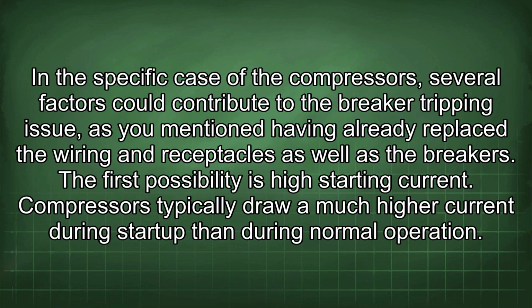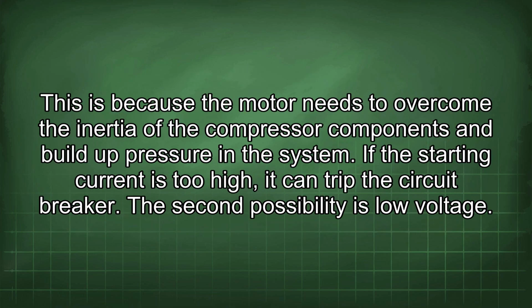In this specific case of the compressors, several factors could contribute to the breaker tripping issue, as you mentioned, having already replaced the wiring and receptacles as well as the breakers. The first possibility is high starting current. Compressors typically draw a much higher current during startup than during normal operation. This is because the motor needs to overcome the inertia of the compressor components and build up pressure in the system.